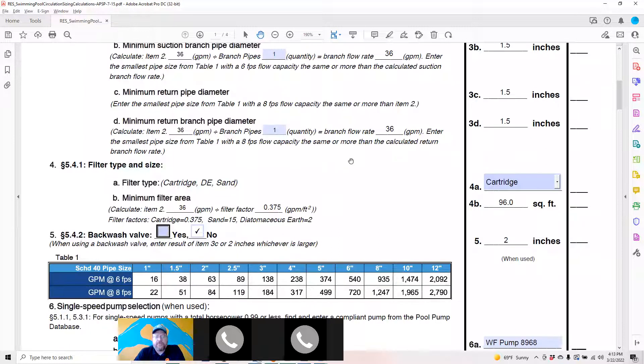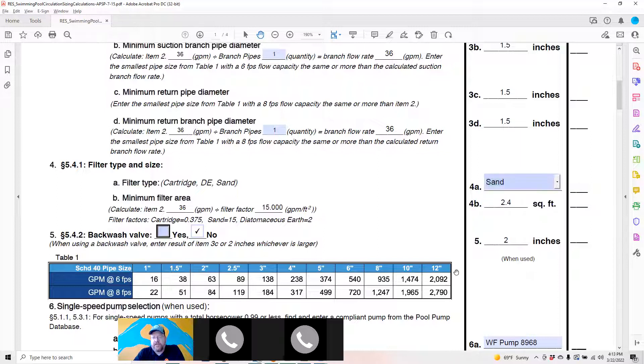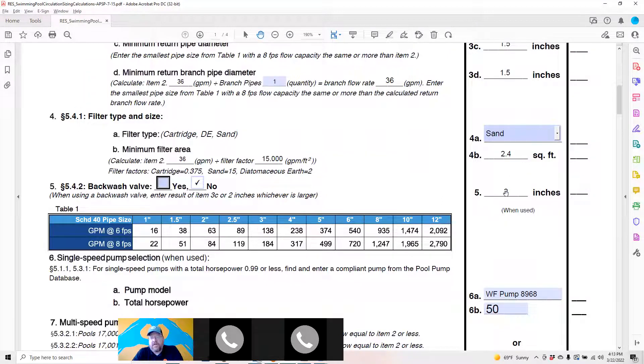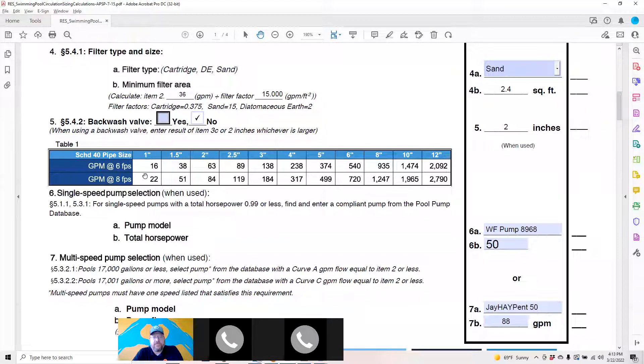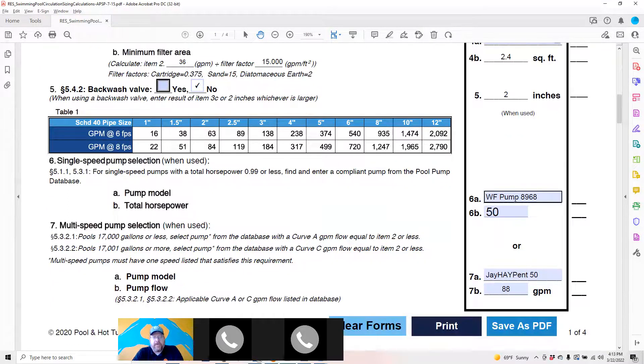Section three, section four is pretty simple. Drop down, choose cartridge, DE, or sand. It'll tell you your minimum amount based off your minimum GPM and the filter factor for it. If you have a backwash valve, indicate here. It'll let you know what the maximum, the minimum size is. Then it gives you the helpful chart in converting pipe diameter and GPM to feet per second and its maximum GPMs here.